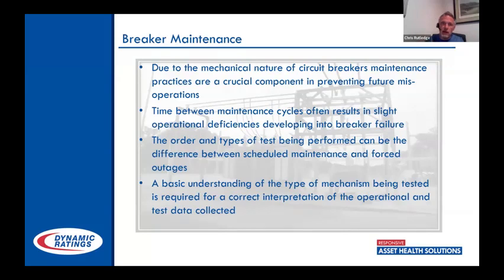Once a fault passes through upstream through the transformer, you've placed all this mechanical and thermal stress on the equipment for extended periods of time. These long periods between maintenance cycles really allow a lot of bad things to happen with circuit breakers. The biggest enemy of a breaker is to sit there in a static state year in and year out, not be operated, and then be called on to suddenly interrupt something in three cycles.